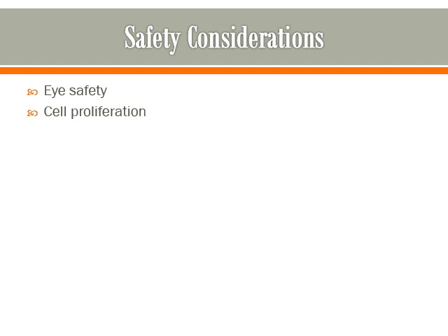Adult dose should not exceed 50 joules. Children under 14, it should not exceed 25 joules. There is potential fatigue reaction. Fatigue has been reported after laser treatment. Usually this was short term and was more common with chronic pain conditions. So we're not quite sure of the connection there, but that's important to note.